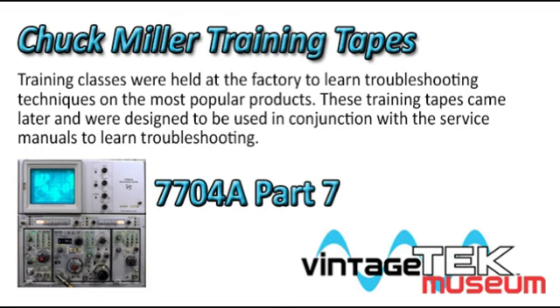Now, that could occur at any portion of the cycle, and it could possibly blow a transistor, but this is an emergency situation. The CRT anode supply is derived from this pre-regulated supply. If this supply goes too high, then the anode supply for the CRT goes too high, and we're in danger of exceeding the X-ray limits set by the government. So it's important that we shut down the supply, even if it means blowing a transistor in the process.